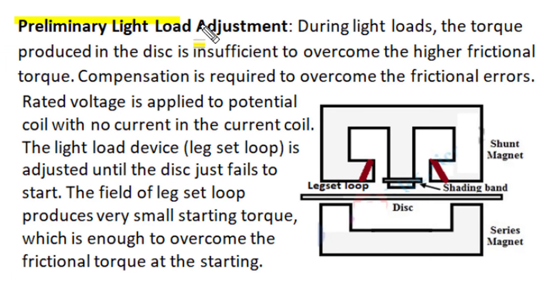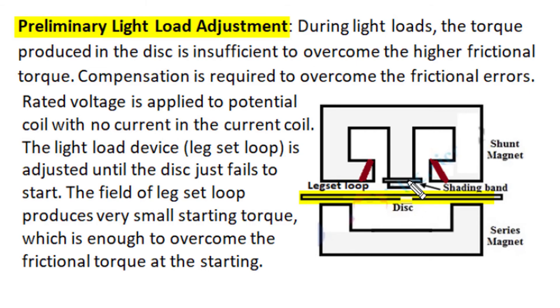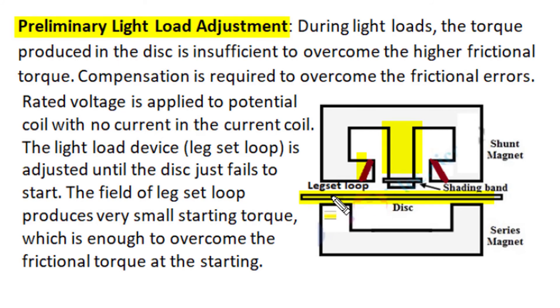During testing of an energy meter, the first stage is preliminary light load adjustment. At light load conditions, the torque produced in the disk is insufficient to overcome higher frictional torque, and the energy meter will read less than the actual energy passing through it. Compensation is required to overcome frictional errors. To adjust the frictional error compensation, rated voltage is applied to the potential coil while the current coil is left unexcited with no current in the load circuit.